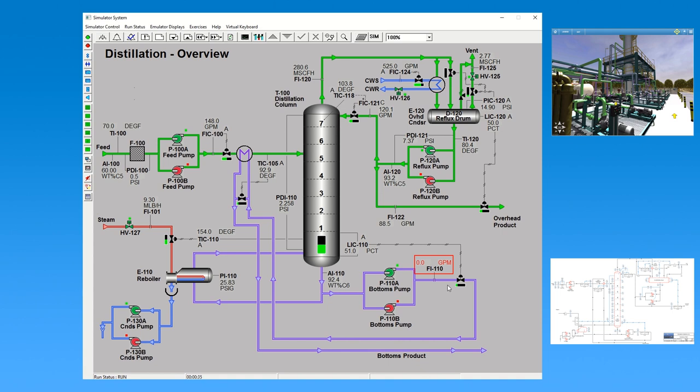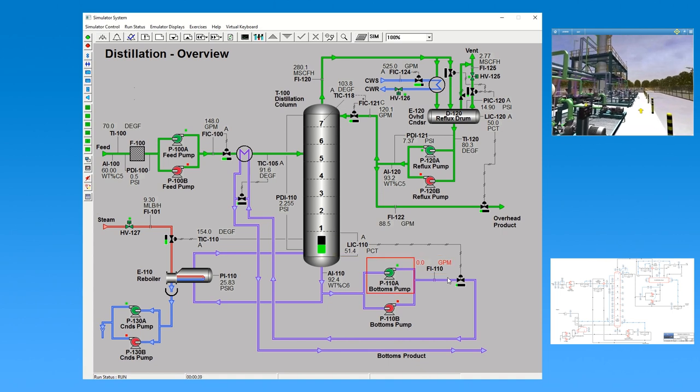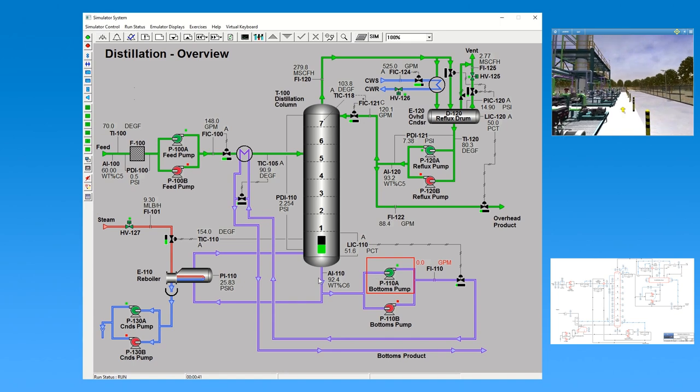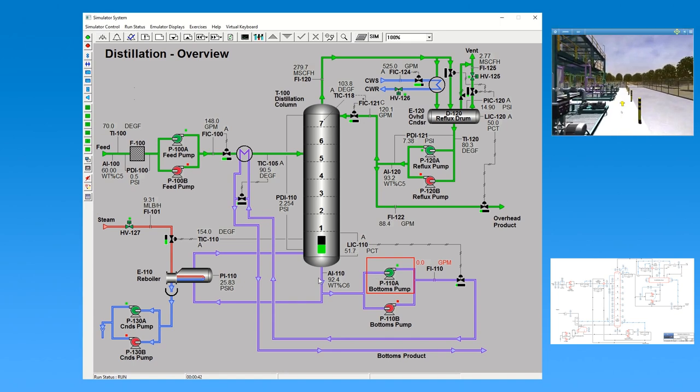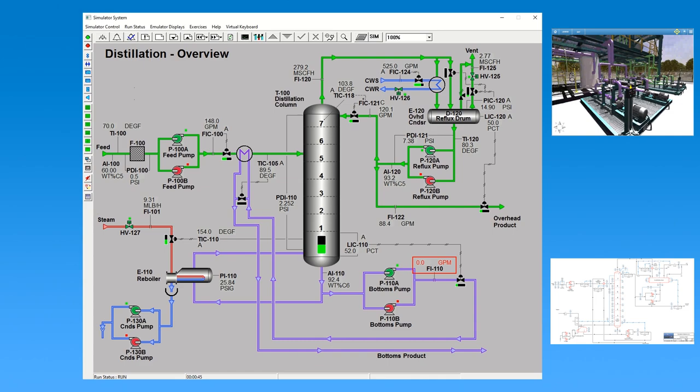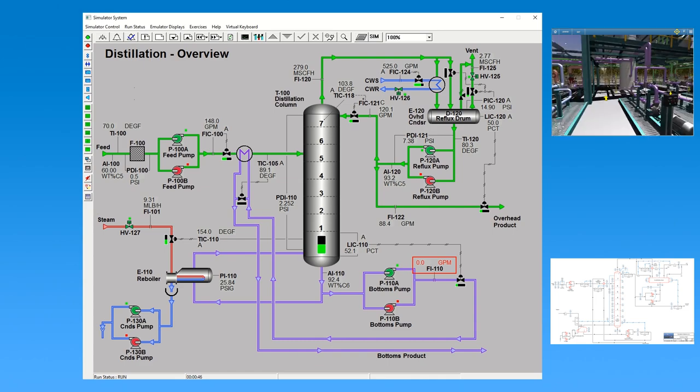The console operator must quickly decide on the best course of action to determine and correct the issue. They may consider: Is there a low, low level at the bottom of the tower? Did the bottom's pump malfunction and should it be switched over to the backup? Is there instrumentation or transmitter error? Did the level-controlled valve fail?